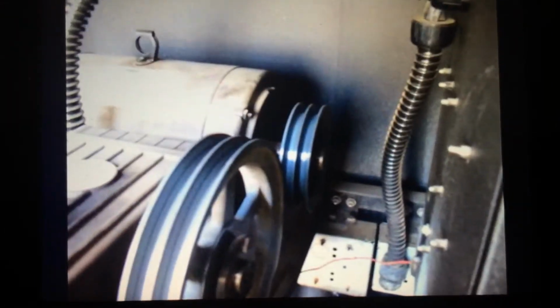If the contactors inside are burned, that could create a voltage and amperage issue that is going to be noticeable in the motor as a symptom. In this case, after we took the wires that fed the motor and put them at the very top of the contactor, we established power from the circuit breaker, a 40 amp circuit breaker, and it kicked the breaker after about 3 seconds. According to our nameplate tag right here, it should have been 25.5 amps maximum under full load, and we kicked the 40 amp breaker. Just to verify that our system is not under any load, you see that we removed the pump belts off of the motor, and we turned the pump over just to make sure that we don't have any lag, and the pump turns very nicely without belts on there. Obviously the motor is able and free to start on its own.